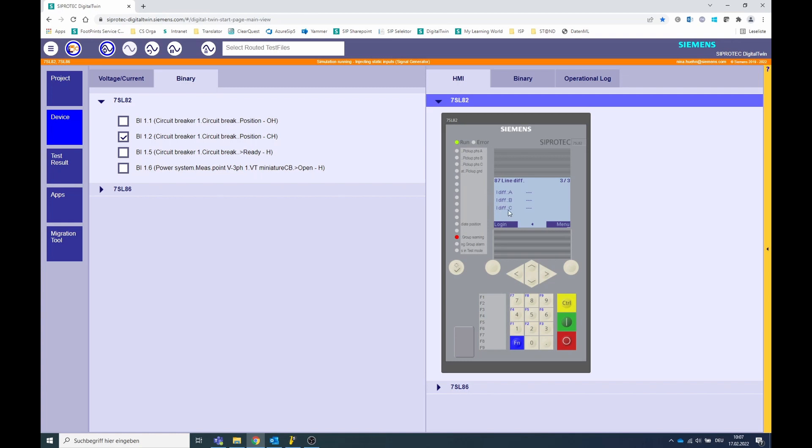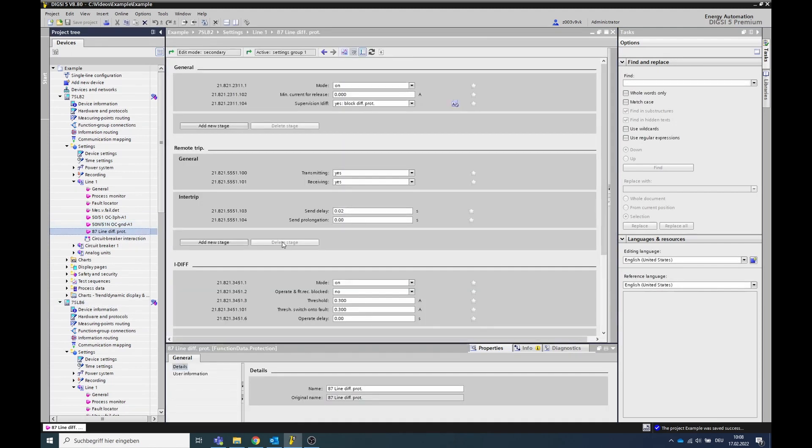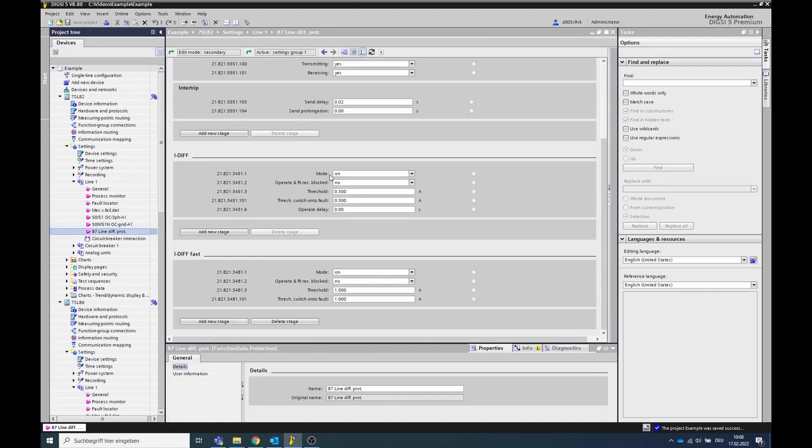Open the configuration files of the affected devices in DIGSI. Go to the line function group and open the line diff protection function. In both devices, check that the function is turned on.